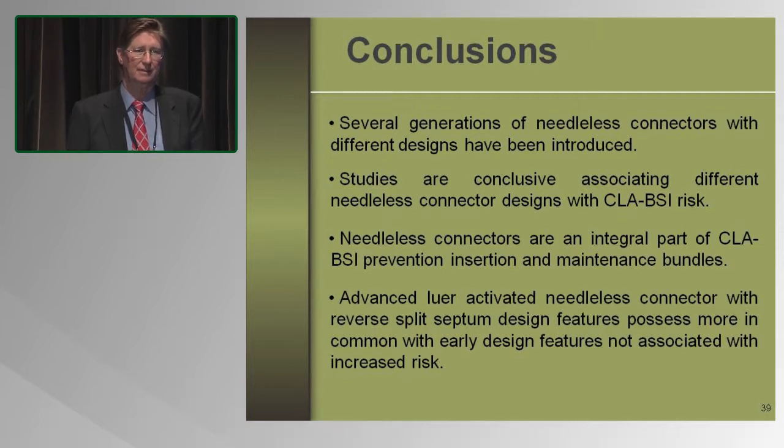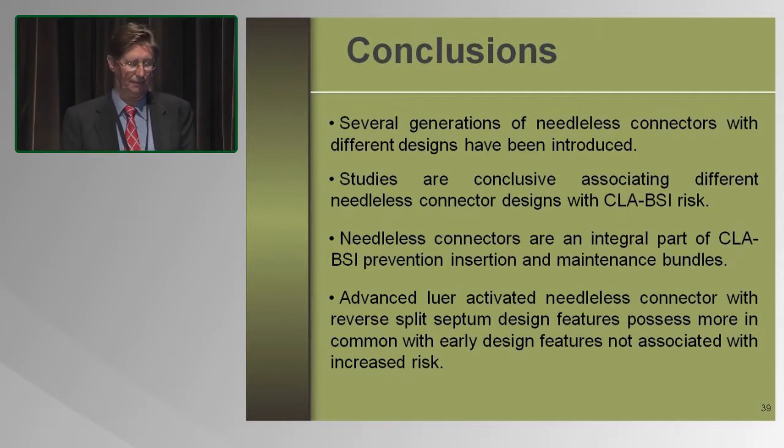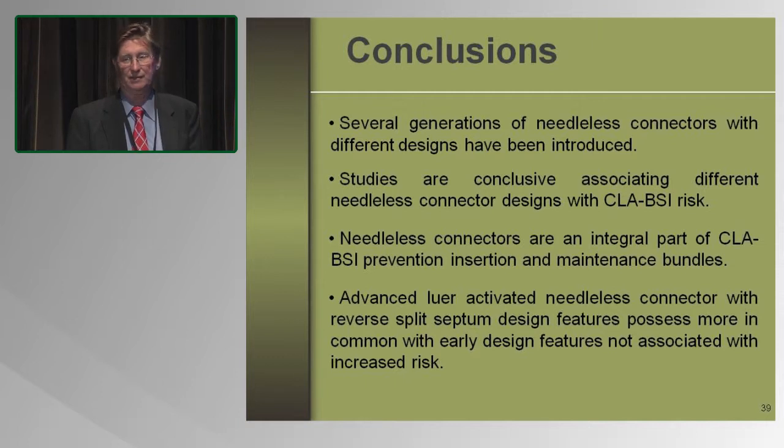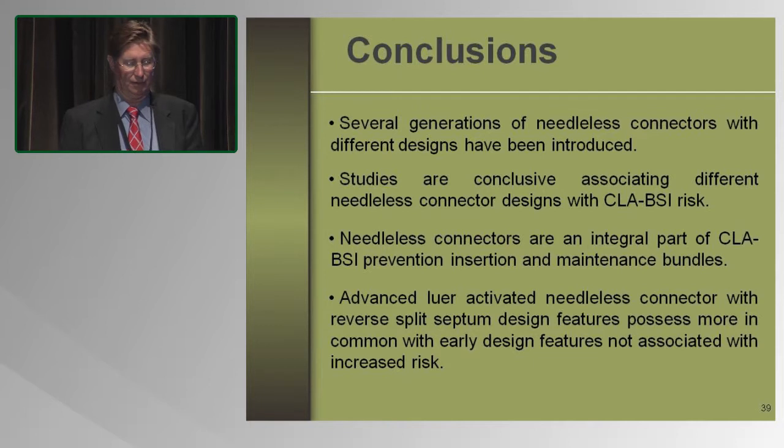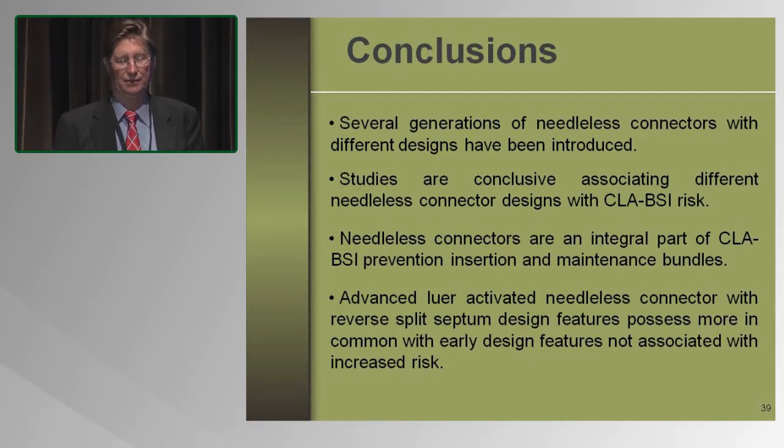That advanced luer-activated needleless connectors with a reverse split septum design feature possess more in common with the early designs that were not associated with increased CLABSI risk.